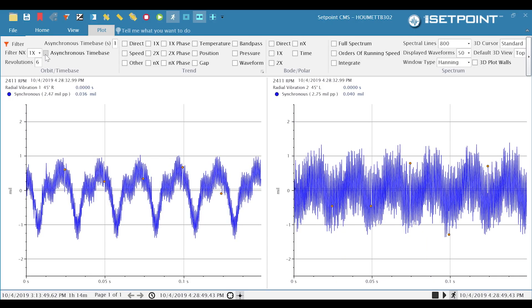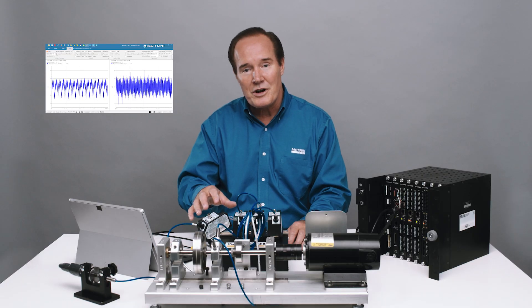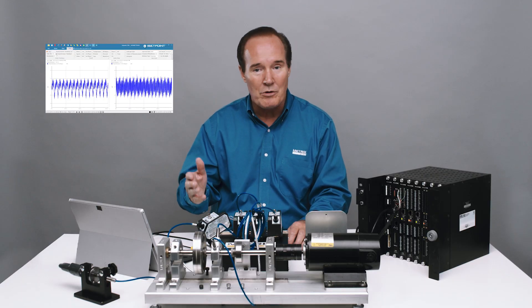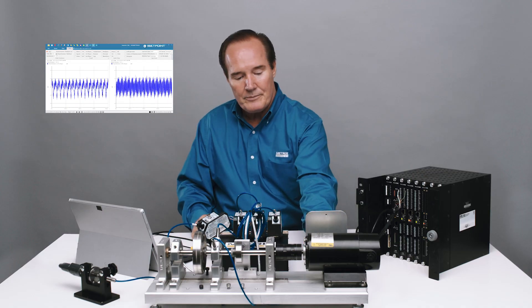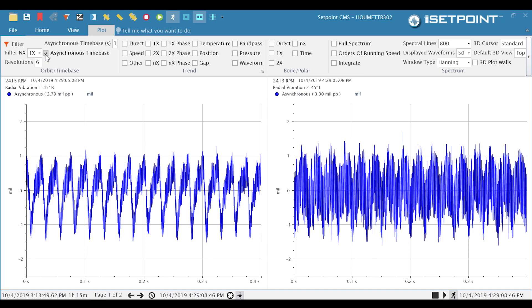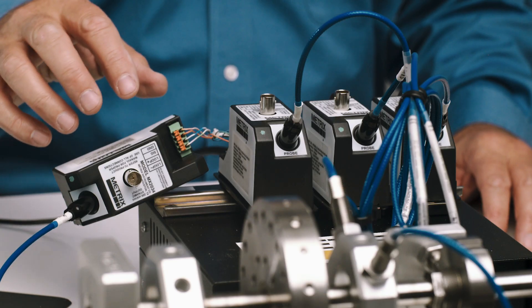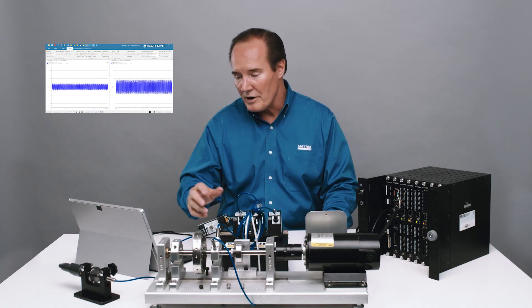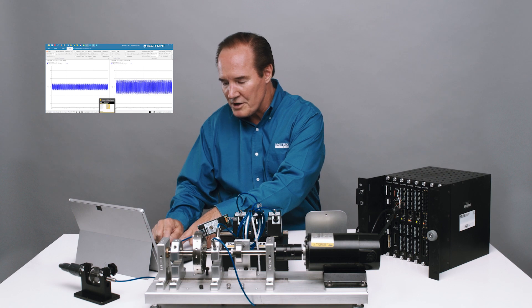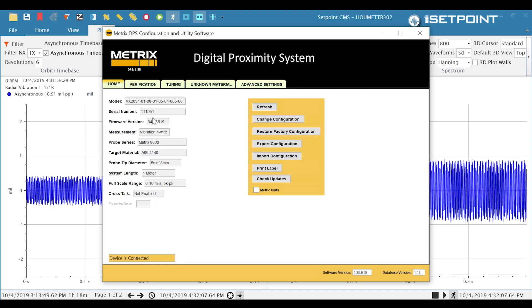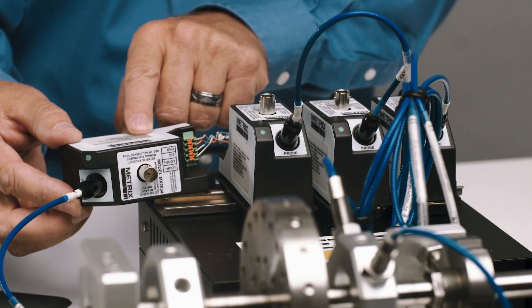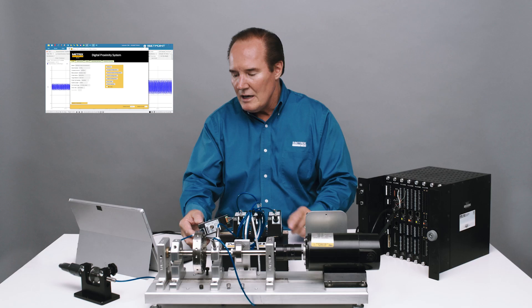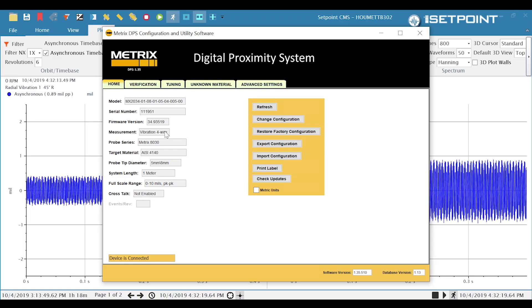So what I'm going to do is shut down and switch the frequency of my Y transducer — switch it from X, which is the normal frequency, to Y, which will force the frequency to be different from the other. I'm going to change the frequency of the Y transducer to a Y frequency to cause a forced separation. To do that, I start the digital proximity system software. We can see on the software that we're already connected — you can see serial number 111951, which is the same serial number on this digital proximity unit. This is vibration four-wire, looking with MX8030 probes at a 4140 target, eight millimeter probe tip, one meter probe.